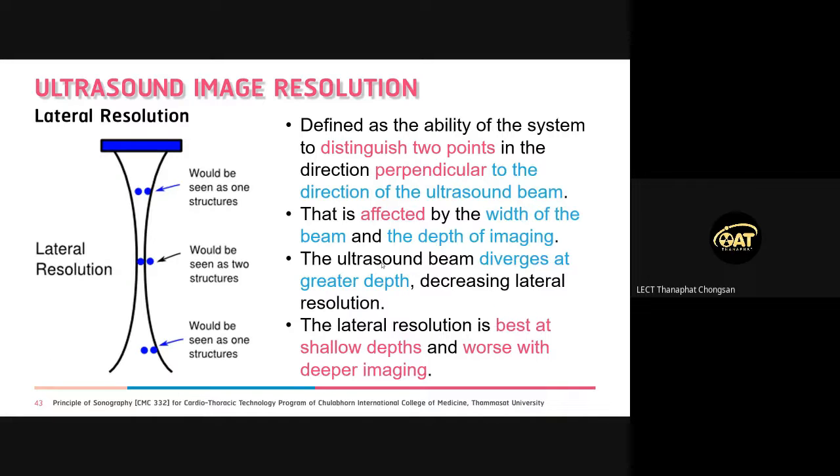Okay. Next resolution is lateral resolution. Lateral resolution is similar to axial, but lateral resolution is the ability to separate one object from another object in the lateral direction, the direction perpendicular to the ultrasound beam. This is the ultrasound beam.